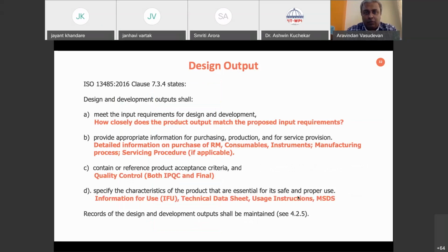For the design output, you have to see how closely the product output matches the proposed input requirements. You write detailed information on how you purchase the raw material, which is very critical, and where you get the raw material from. What kind of consumables are you using? What kind of instruments are you using? Is there a service provision in place? What kind of quality control procedures do you have in place for both in-process control and the final product? What characteristics are necessary for safe and proper use? So the information for use sheet, which you find inside a medical device, is very important. The technical data sheet, of course, usage instructions and MSDS. These are all part of the design output.